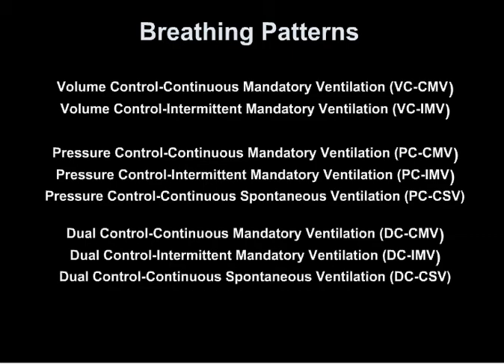There are eight distinct breathing patterns: volume control CMV, volume control IMV, pressure control CMV, pressure control IMV, pressure control continuous spontaneous ventilation, dual control CMV, dual control IMV, and dual control CSV.